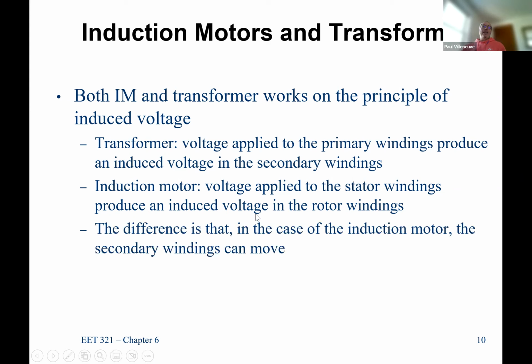So why is that a similar concept? Well, because it's primary, secondary, stator to rotor. It's the same concept. What we see here is in an induction motor, the secondary windings can rotate. So when you think about a transformer, what's the electrical frequency going to be on the secondary of a winding? What would you guess is the frequency of the secondary windings? Should be the same. Yeah, 60 hertz, right?